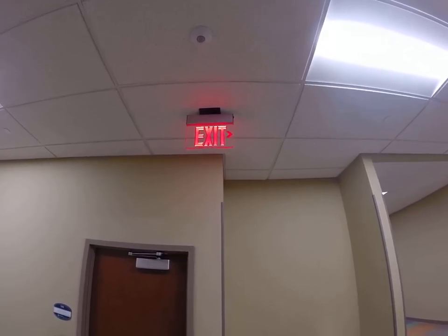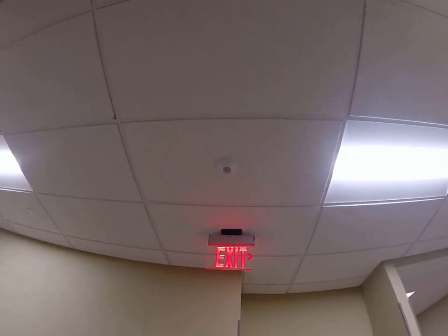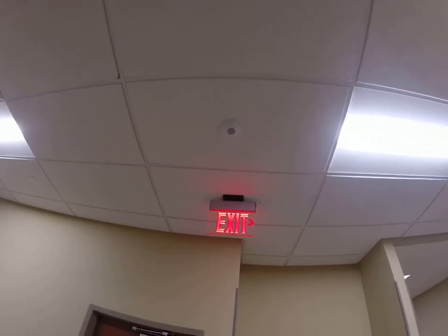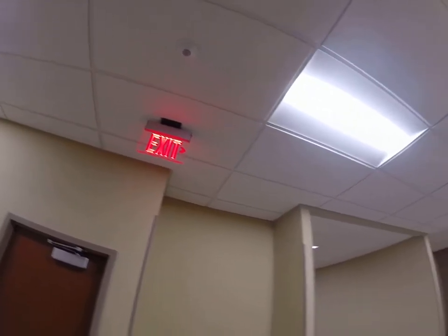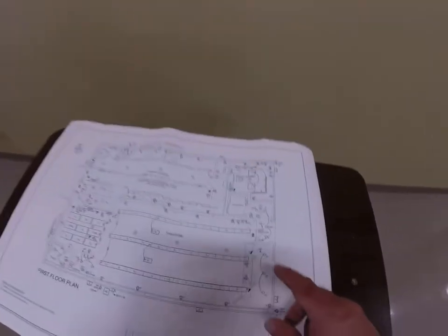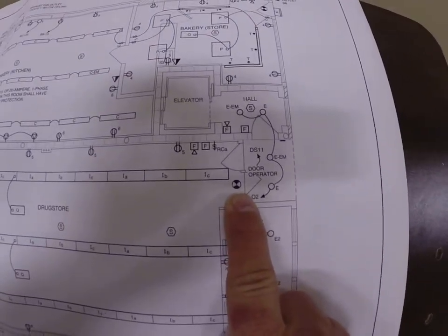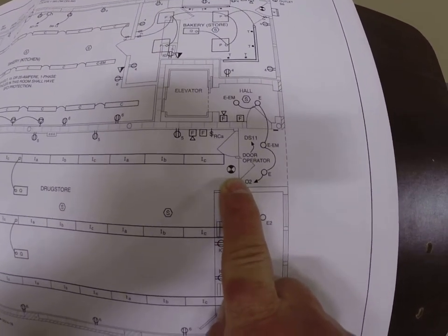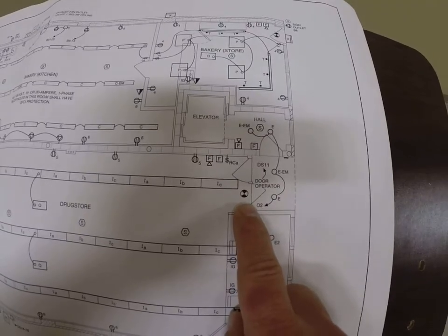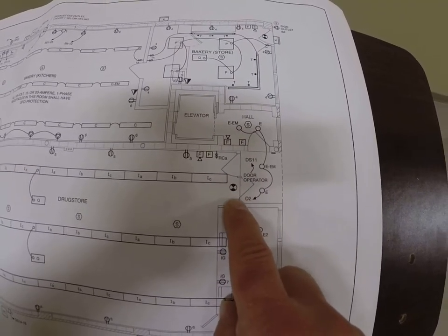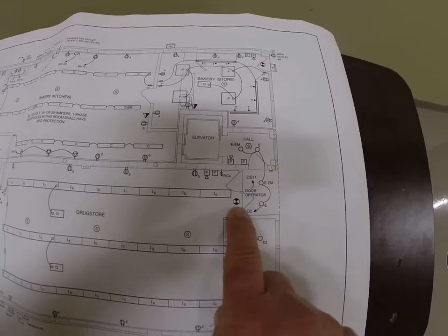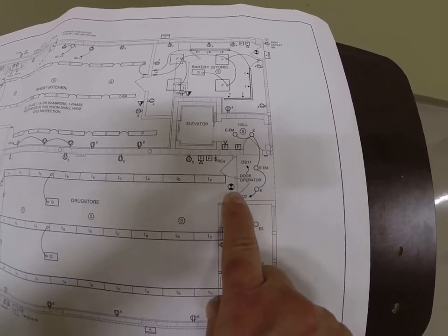I'll show you that symbol on the blueprint next, as well as an occupancy sensor, which is right next to it in the tile adjacent. That keeps the lights on when it senses movement. So as we go down and check out where those symbols might be on a typical blueprint, we could see this symbol right here represents an exit sign, very similar to the one I just showed you. This denotes, with this particular symbol, that the exit is left to right or both directions, so you can see it from either direction. So keep in mind that that really makes you realize how the exit sign is supposed to face.